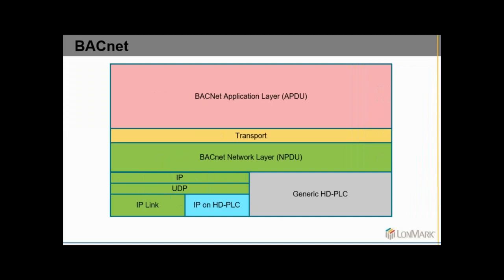The first approach is pretty simple. As HD-PLC is tunneling Ethernet, we can use natively BACnet IP on HD-PLC. So it's a usual IP link which is transferring UDP. You don't even need to have a BACnet router from BACnet IP to BACnet HD-PLC, because that would be just a media converter like that. The other thing which is actually evaluated in parallel is to make generic HD-PLC BACnet frames, once again transporting the NPDUs. That's not pretty ready, but the first prototype is already running.